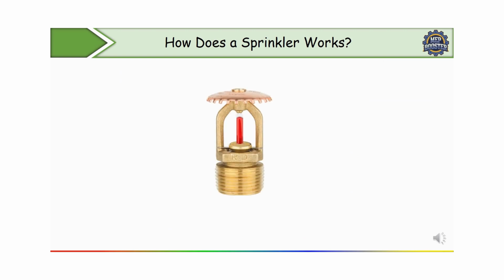Here also it is shown. As I told you, each sprinkler head is equipped with a trigger mechanism, typically a glass bulb or a fusible link. In this figure, the sprinkler which I have shown has a glass bulb. The glass bulb contains a liquid that expands and bursts at a specific temperature. When the temperature at the sprinkler head reaches the activation point, usually between 155 degrees Fahrenheit and 300 degrees Fahrenheit, depending on the type of sprinkler, the trigger mechanism activates. It opens a small valve within the sprinkler head, allowing water to flow through.